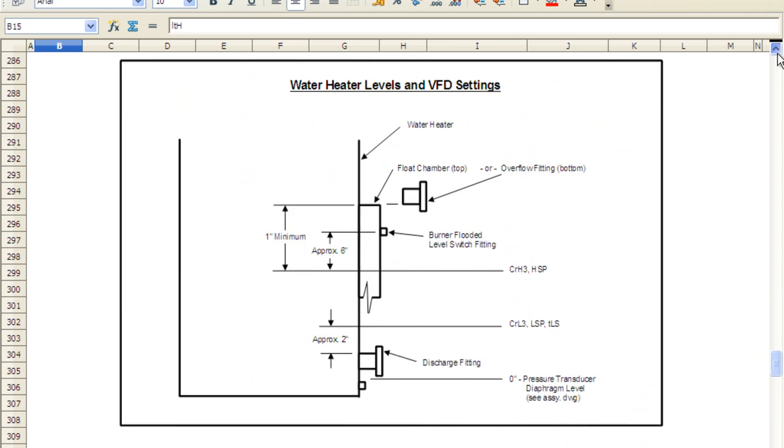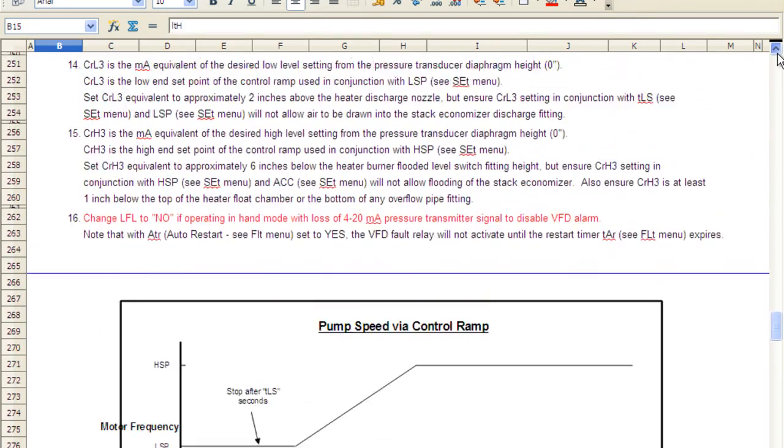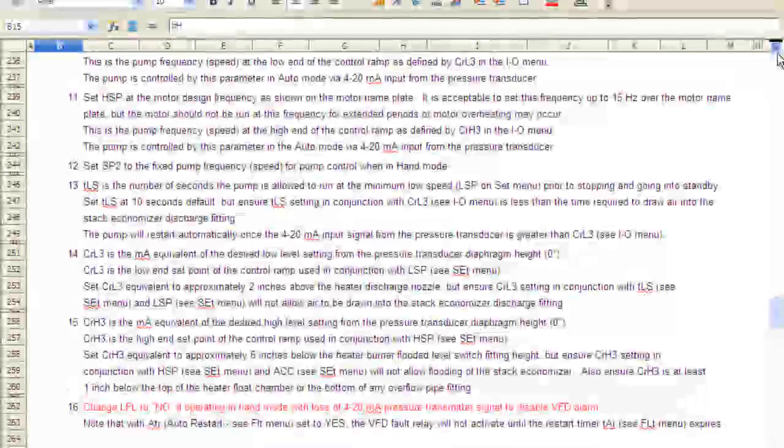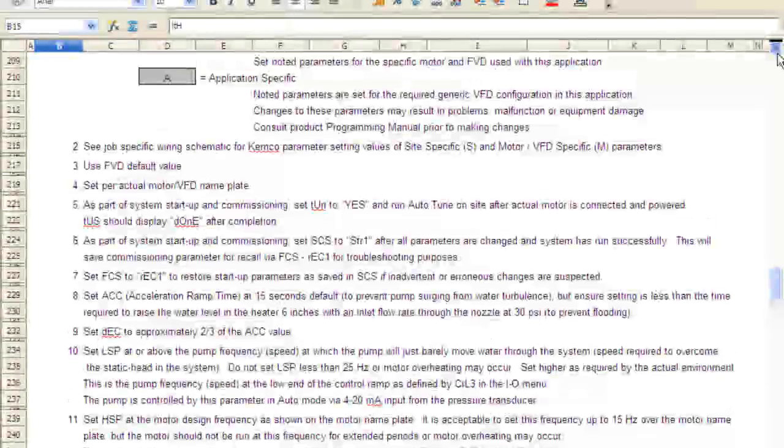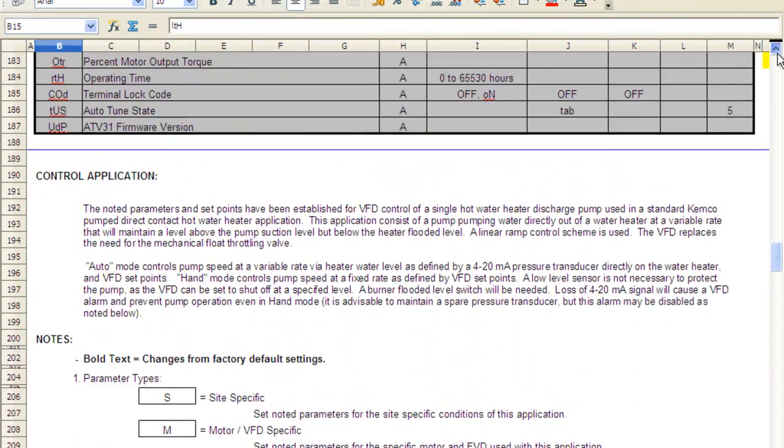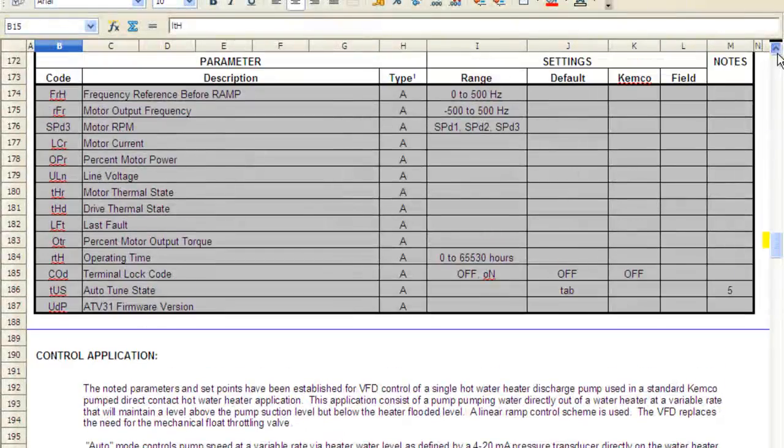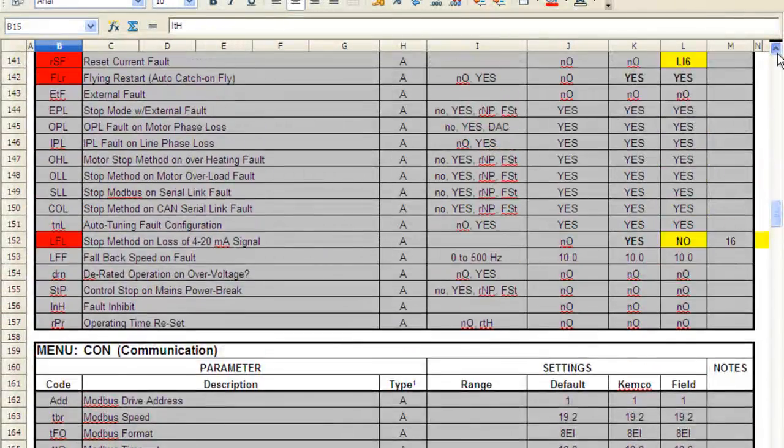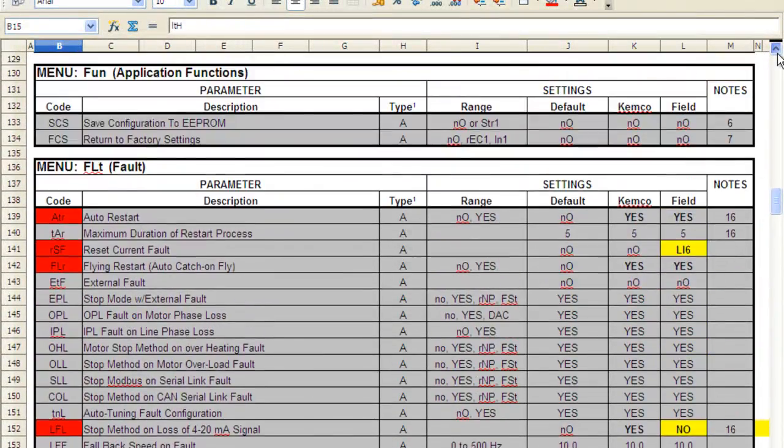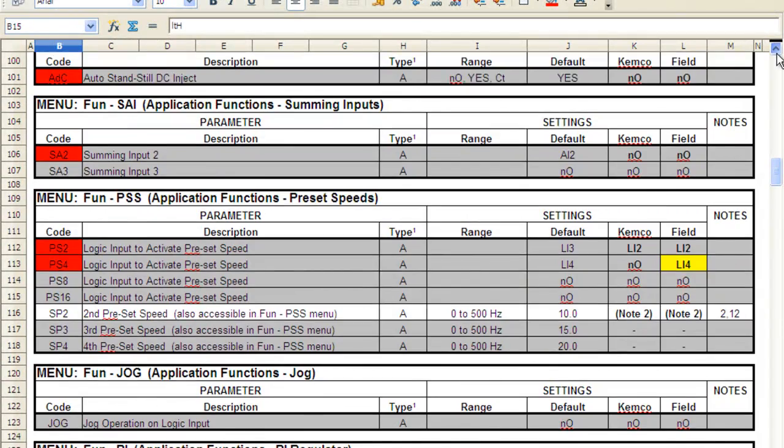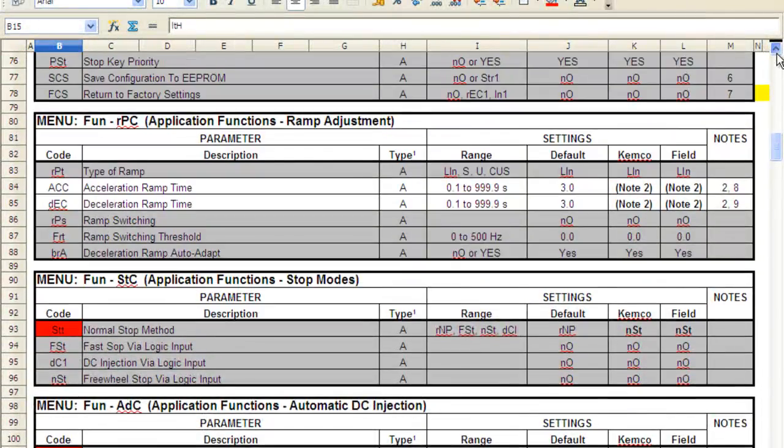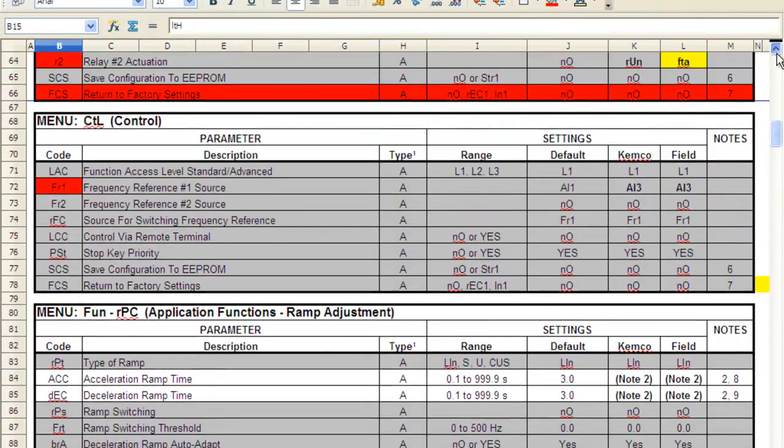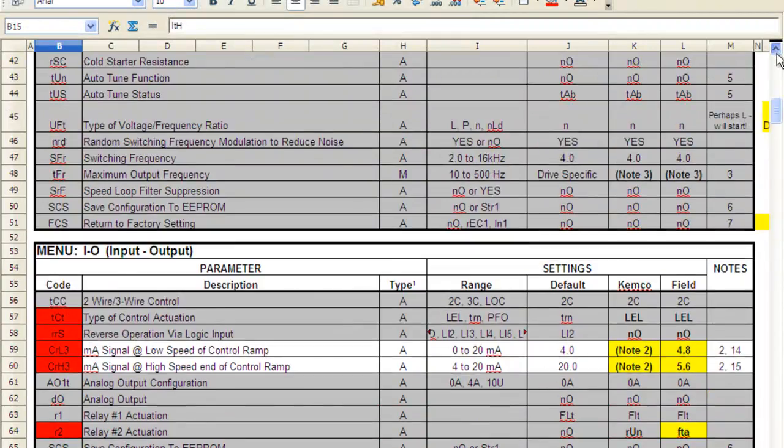There's a video coming behind this one which we've entitled VFD number 2 navigation of the drive, which is going to show you the buttons on the drive to push that are outlined in this procedure. But basically the drive has 7 primary menus which you can navigate through, and then one group in a menu has another 6 or 7 sub menus. We'll talk about that here in a little bit. And in the example we went through the exact button pushing to change these two milliamp readings.